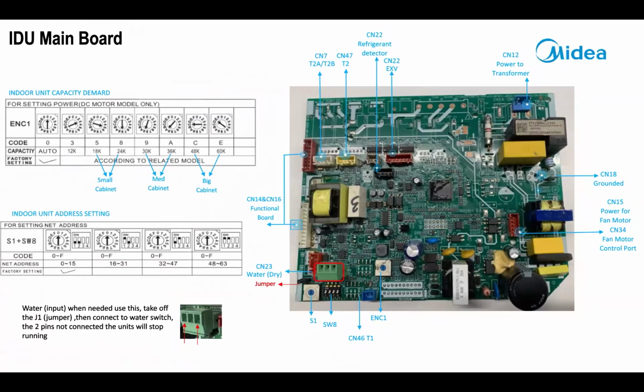All right, main board. There's your interconnecting cables, CN14 and CN16. Through the middle, the white is the white terminal. Marked CN7 is your T2A, T2B. Number 47 is T2, that's the yellow one. The black terminal, right about the middle of the board, is your refrigerant detection sensor. That is a communicating sensor, guys, so don't think you can bypass it, because you can't.